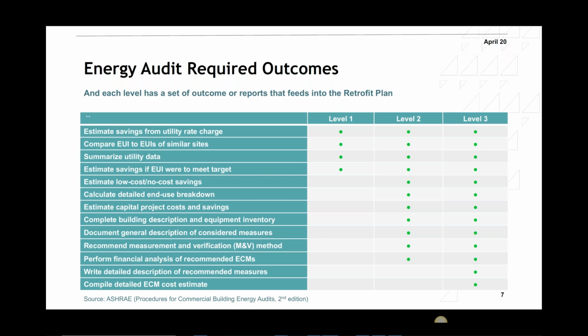Estimate capital project costs and savings—how much it's going to cost you, let's say, to change the chiller. What are the savings? What is the O&M? O&M could increase or decrease. If you're buying a new chiller and replacing a really old air-cooled chiller, probably the maintenance will go down. But if you're adding an absorption chiller, maintenance will go up because you need expertise for that.